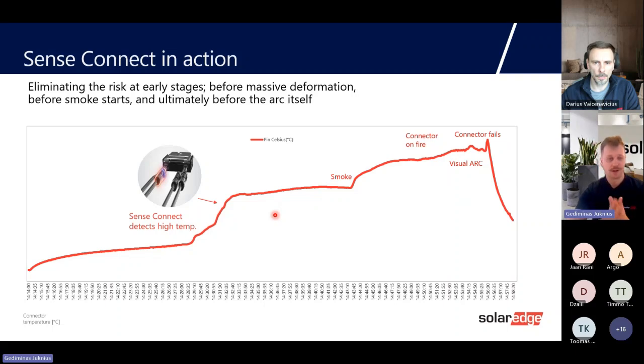So let's do some job. Let's think how we can avoid it. And we did a great job. We found a new technology. It's called Sense Connect. Every optimizer S series contains temperature measurement equipment, so temperature sensors, and it measures 10 centimeters away from the optimizer. And if the MC4 connector starts to heat up, the threshold is approximately 200 Celsius. The optimizer will send the data to the inverter, and the inverter will shut the string. So even before the smoke, before the arc, before the fire, the production will be stopped immediately, turned to safe DC, and you will get into the monitoring that this exact PV module, at that specific location, has an electrical arc or a faulty MC4 connector.